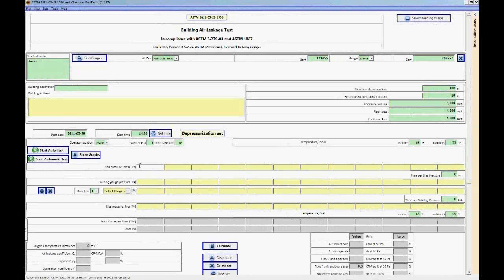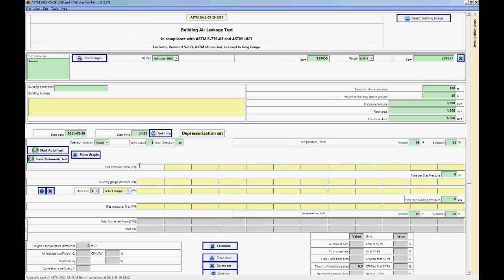However, we do recommend taking a slightly longer bias pressure. So if you set your gauge up to read a time average of 20 seconds, then you have to wait at least 20 seconds before taking the reading down. So let's say we did that in the field and we read a bias pressure of 0.5.